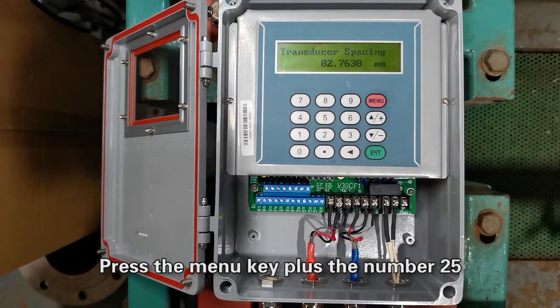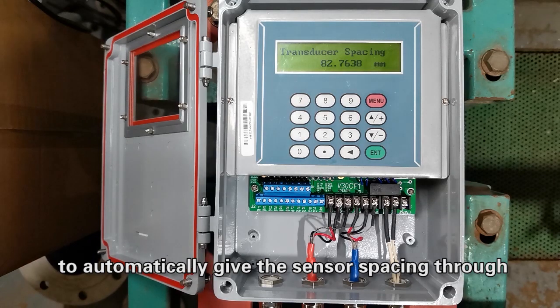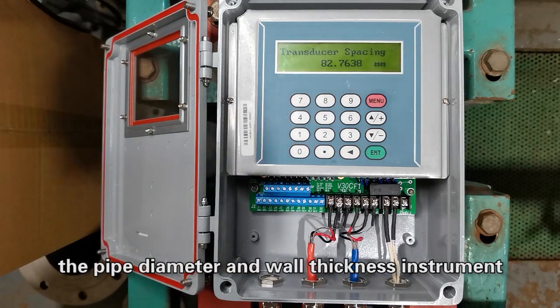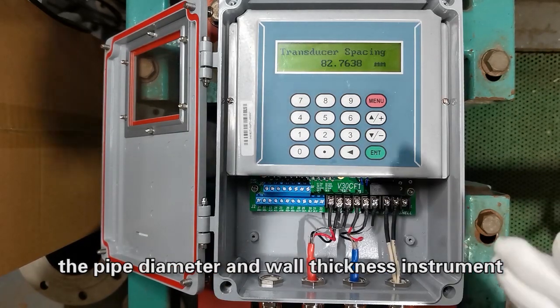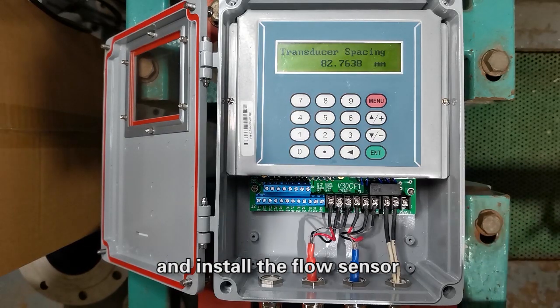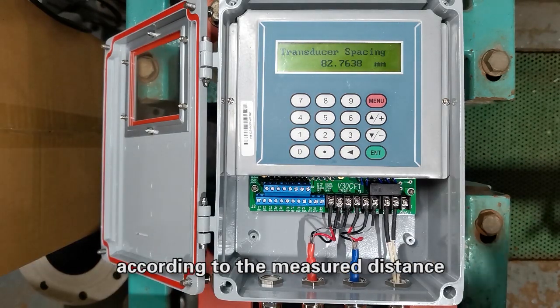Step 9. Sensor installation spacing. Press the menu key plus the number 25 to automatically give the sensor spacing through the pipe diameter and wall thickness instrument, and install the flow sensor according to the measured distance.